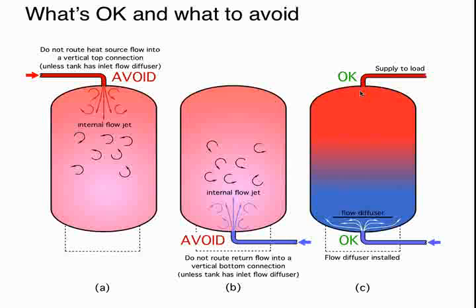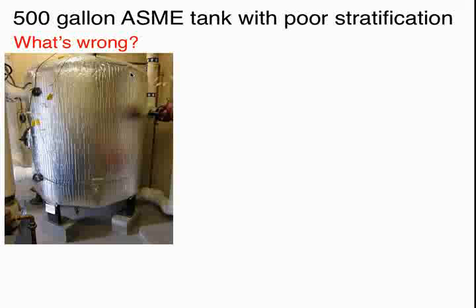Up here at the top, it is fine to take heat out of the tank, to take flow out of the top of the tank, because we're not creating localized high velocities with that, especially if we're just 2 or 3 inches away from that inlet, our velocities are still relatively low. So basically stay away from this and stay away from that.